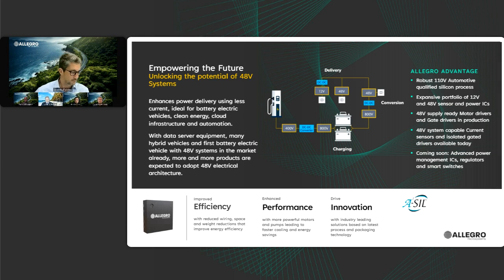So it's probably the backup battery technology that runs at the higher voltage, and then you step it down to 48 and use it across the systems? Correct. And normally on the rack, they run at the 48 volt system because that's where you can do hot swapping, for example.